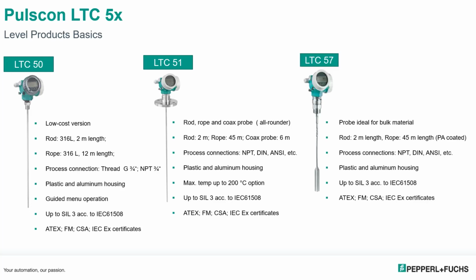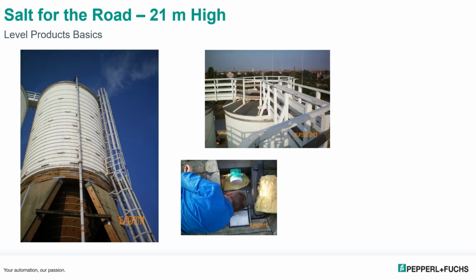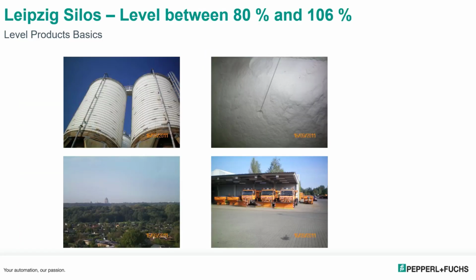And then the LTC 57, mainly used for bulk material, rods 2 meter length, the rope is 45 meter length, PA coated for the bulk materials, DIN, NPT, G threads, and so on. SIL 3 along with the HAZLOC certifications. Here's an application with one of our LTC 57s on a salt silo, about 20 meter high, and you can see it positioned there. Again, you can see the silos and the upper right hand corner, that's cable coming down detecting the salt. Because this is a cable and it's bulk material, many times this cable will come down, it'll be tied off on a weight, and the weight can be tied off to the bottom of the tank so that it doesn't move around or get tangled up in the bulk material as it rises and falls.